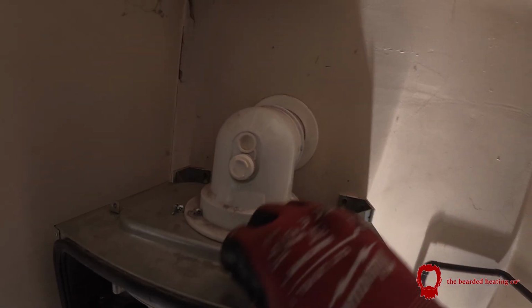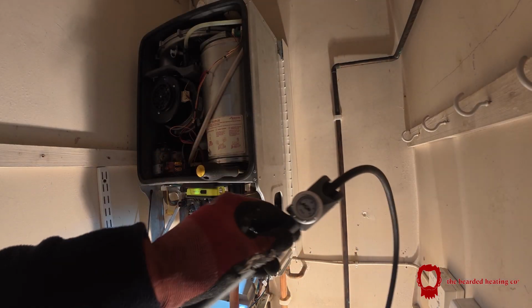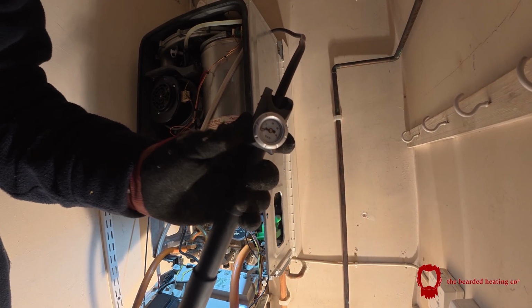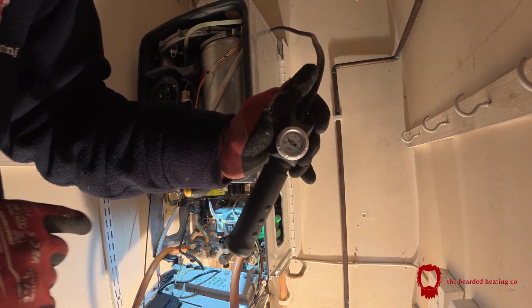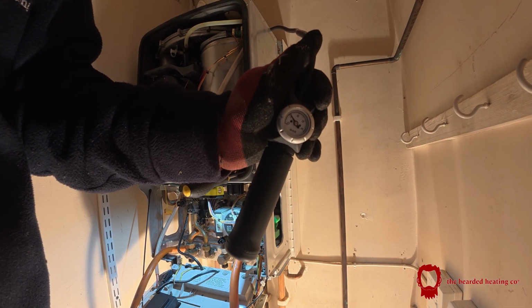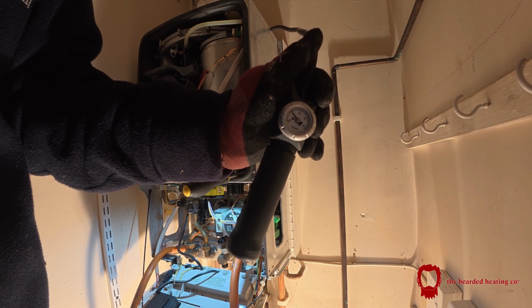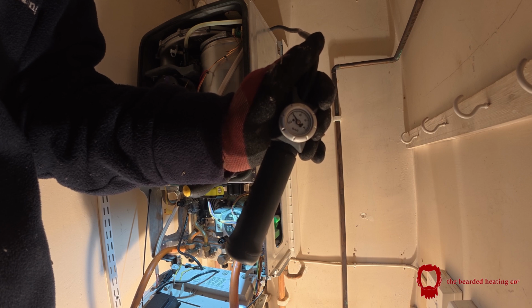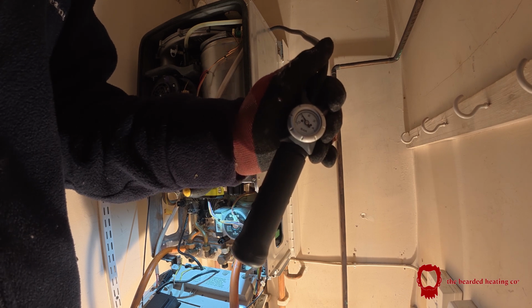I'm going to recharge the vessel. Sorry for the bad lighting, I'm in a little cupboard. Regan pump, and it's flat as usual. You can hear the gurgling now and the expansion vessel pressure. 1 bar, gurgling has stopped. Now I'll just put some leak detection fluid on the Schrader core to make sure it's not passing. Expansion vessel's done.